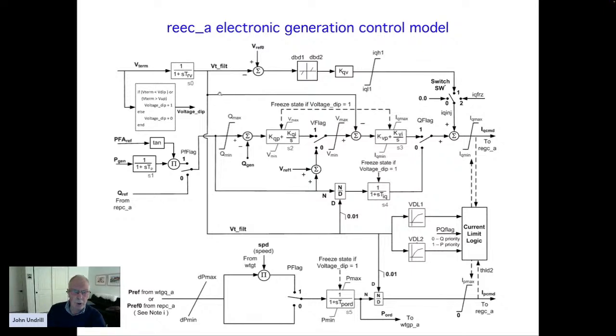This controller operates in the droop relationship. You don't see the droop. You see the reciprocal of the droop. But this sheet of transfer function information is how the inverter would be controlled in an electronic solar generating facility to cause that facility to operate according to the droop law, where the speed goes down with a slope of 5%. Well, that diagram is presumably authoritative. I understand it if I really need to, but most of the time looking at it gives me a sore head.